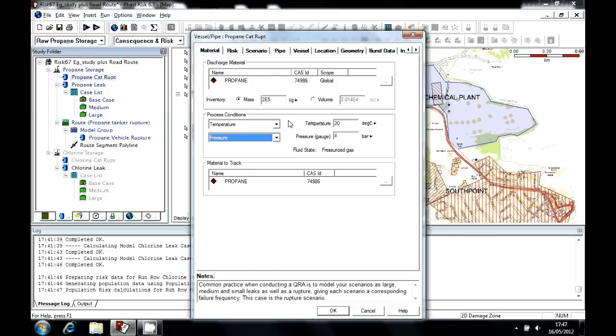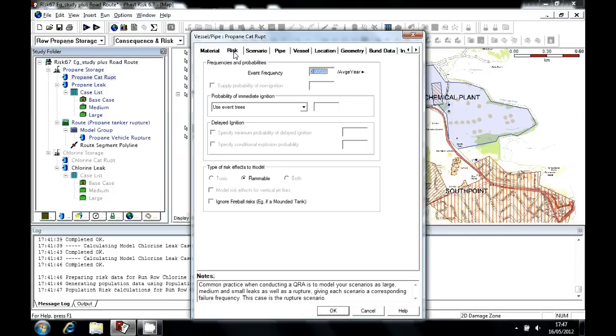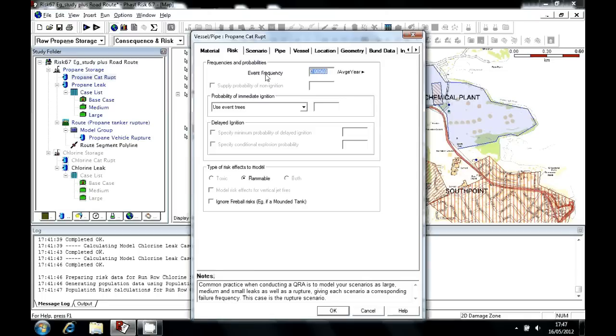Here on the Risk tab of this release case, we give an event frequency. So this is the likelihood, per year, with which this event can occur. You can typically get this number from a historical failure frequency database, or through a method such as fault tree analysis.